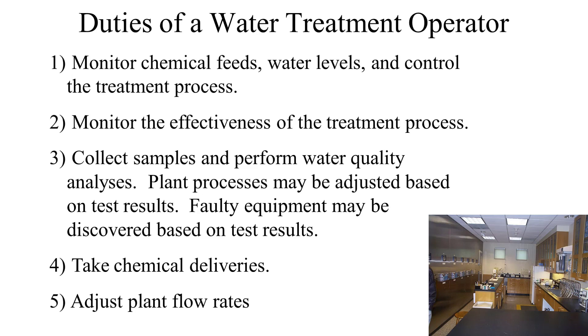The operator has two main sources of information to monitor the processes at the plant. Online, or continuous monitors, are instruments positioned throughout the plant. They constantly test the water and send information to the computer system controlling most plants. The operator monitors flows and water quality data on the plant computer and must react quickly when they notice a problem.